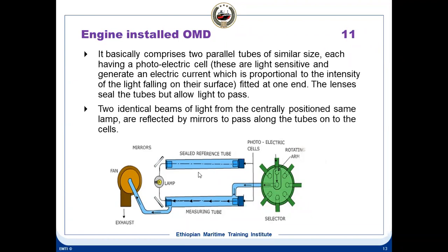But any alarm on the oil mist has to be investigated. We have to come down and check, because there is no other way to check these alarms. But you'll always find a fault alarm will come as a fault alarm. That means equipment failure, anything. Suppose the lamp goes off or the fan is stopped, you'll get a fault alarm. When the concentration goes high, you can see a visual display also.